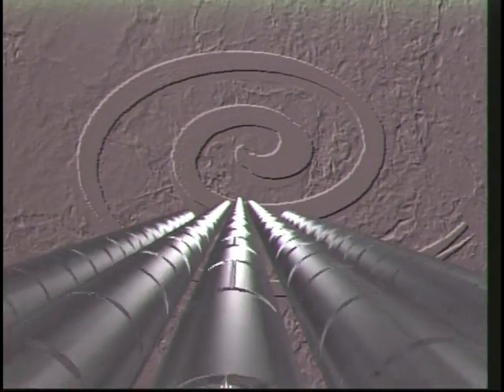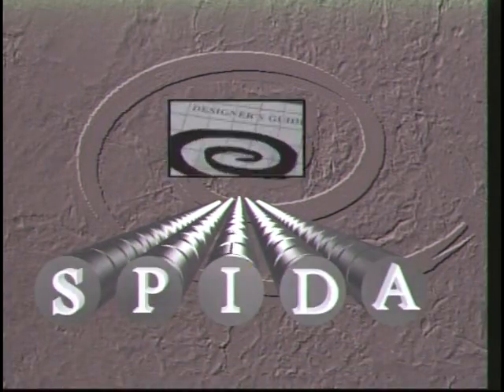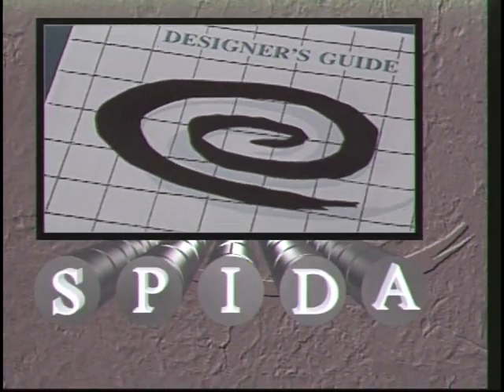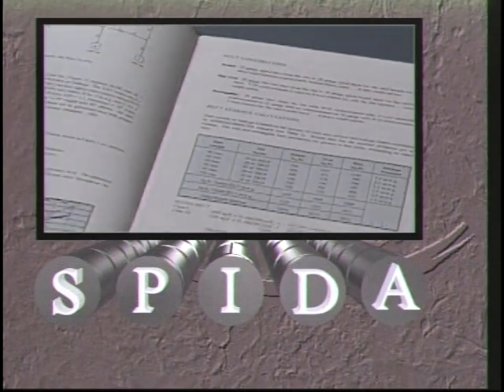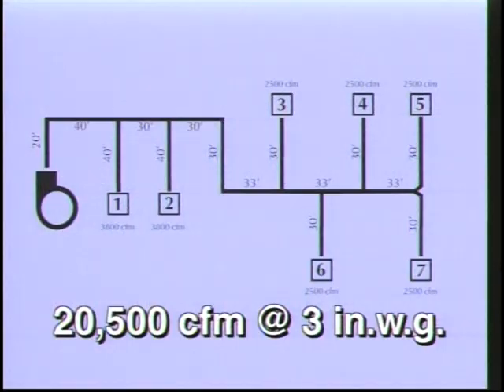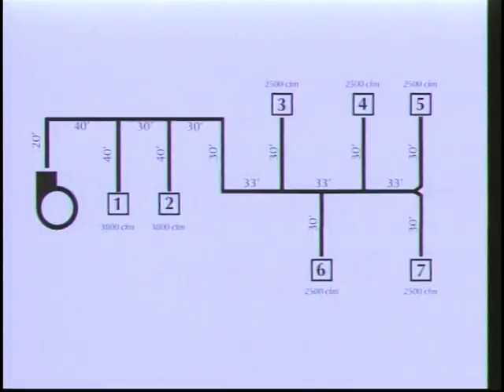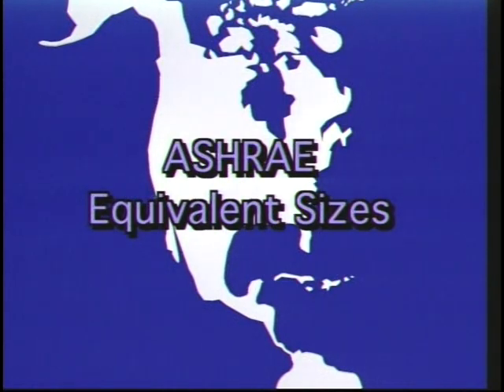The SPIDA brochure entitled Designer's Guide contains a sample variable air volume, often called VAV, supply air duct system, that furnishes 20,500 CFM of air at 3 inches water static pressure. Estimated costs for the use of 3 different types of ductwork were obtained from 9 qualified sheet metal contractors located in major cities throughout the United States and Canada. All duct sizes were based on ASHRAE equivalent sizes and all had approximately the same static pressure drop.